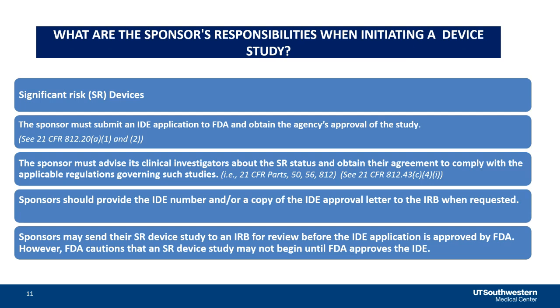device. The sponsor must obtain from all investigators conducting this research at each site an agreement to comply with the status of the device being a significant risk device and comply with all applicable regulatory requirements. Sponsors must also provide the IDE number and a copy of the FDA IDE may proceed letter to the IRB.